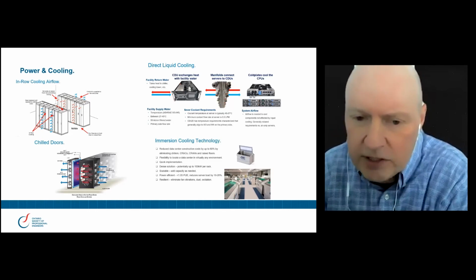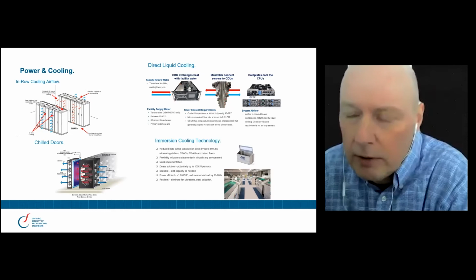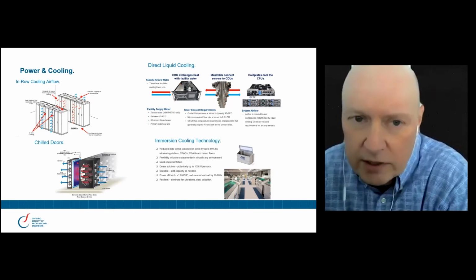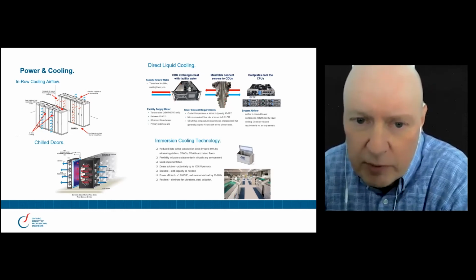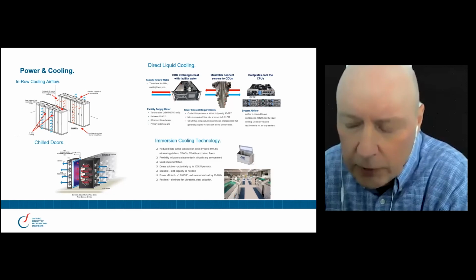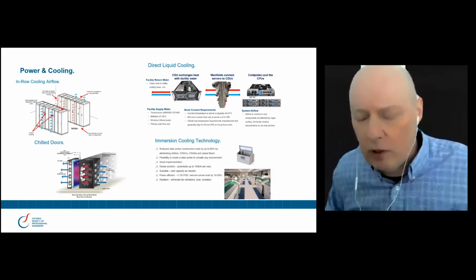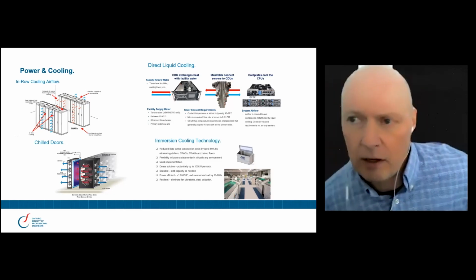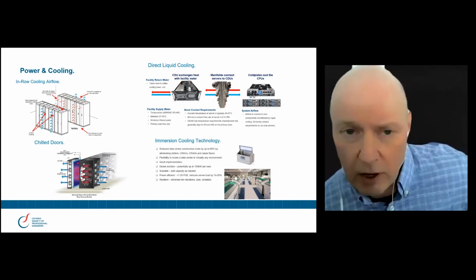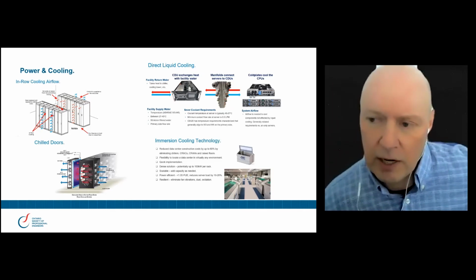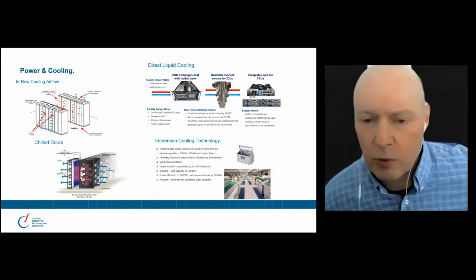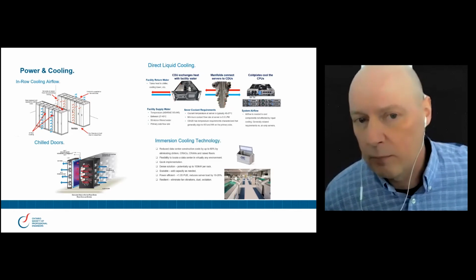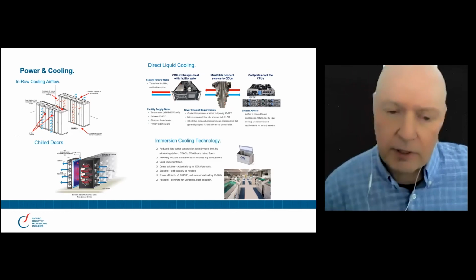And really, any CPU, because they're smaller, anything above 300 watts as we move forward is going to require some amount of liquid cooling. Air cooling will continue to be, of course, available and an option, but it will be increasingly relegated to supporting the lower performance computing solutions.